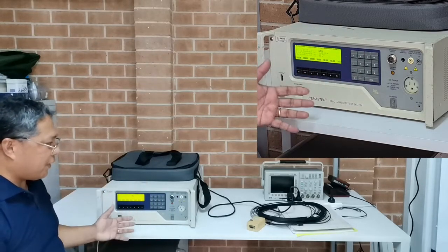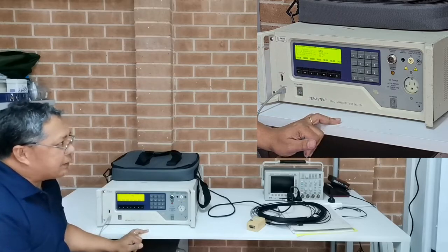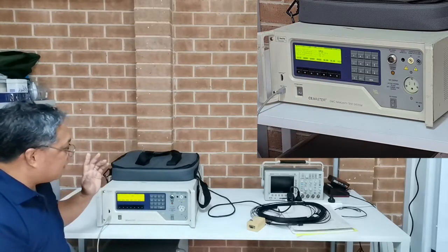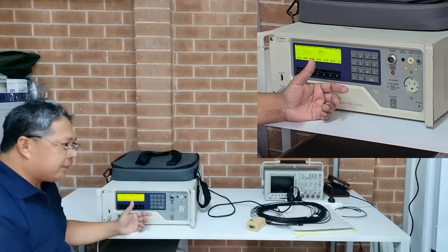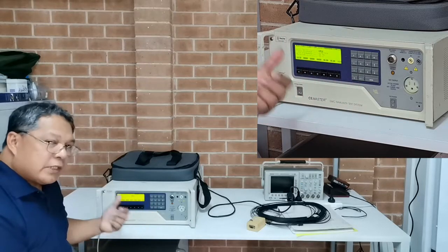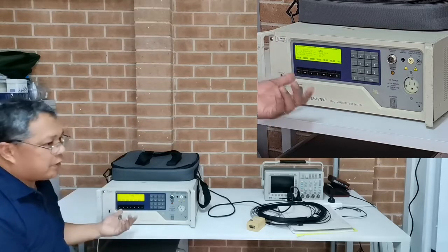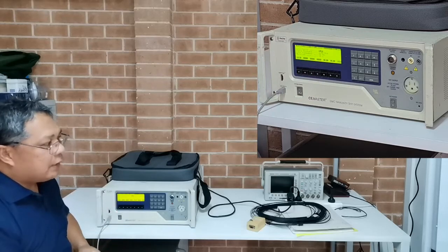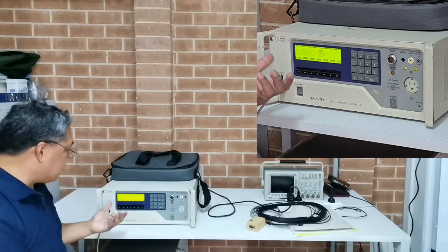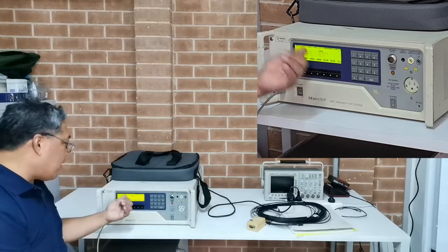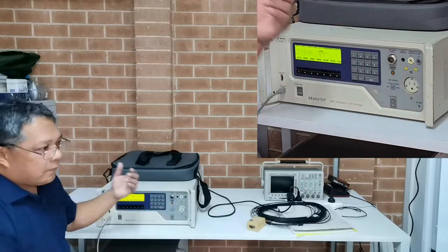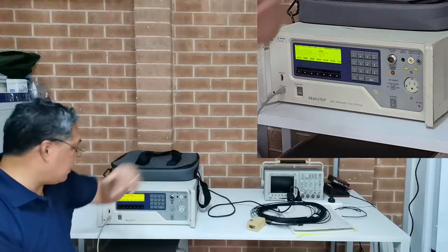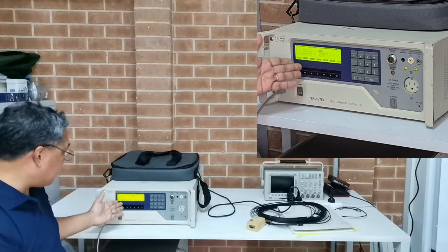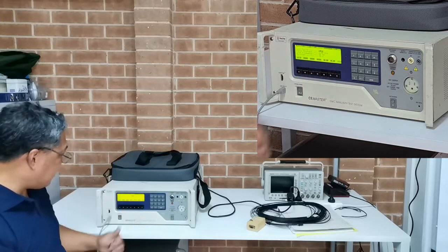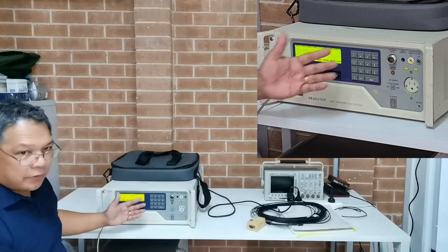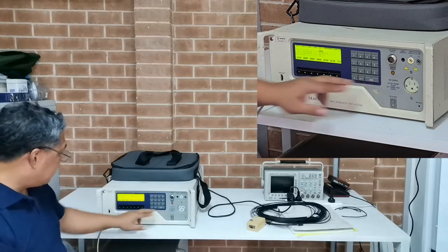Most of the loops have a coil factor for the 1 meter, but off the top of my head I can't remember, sorry. You can work it out by using a microtesla meter and converting that microtesla into amps per meter, and then you work out how much coil factor you need to add in here in order to give the right amps per meter into the magnetic loop. You can also set the line frequency, 50 Hertz, and the duration, which is 30 seconds by default. So we can try to run this one.